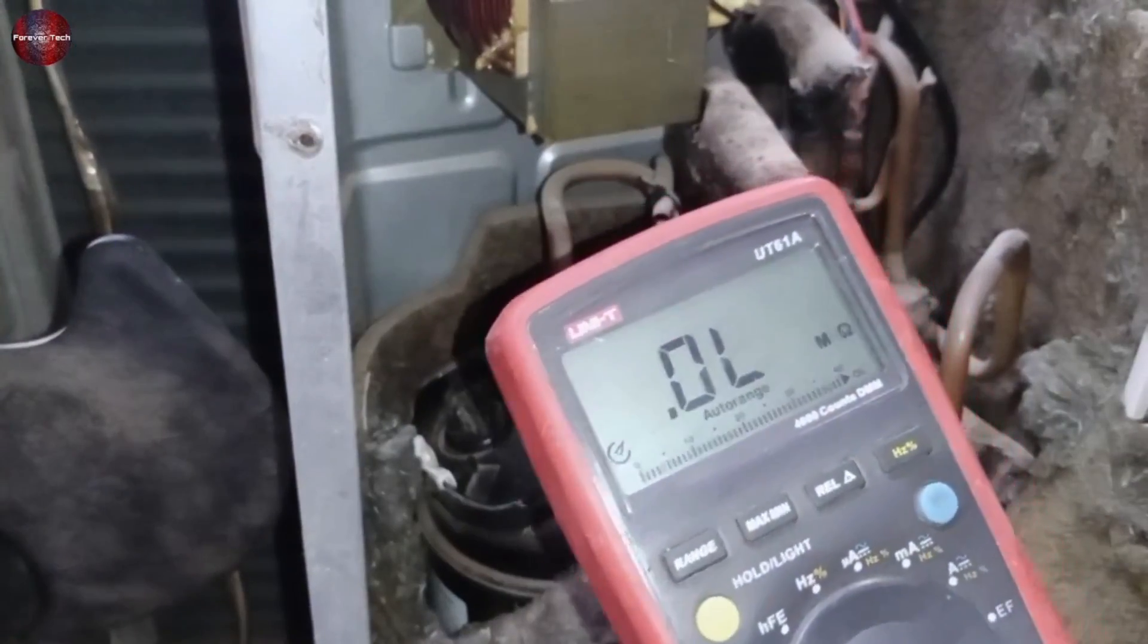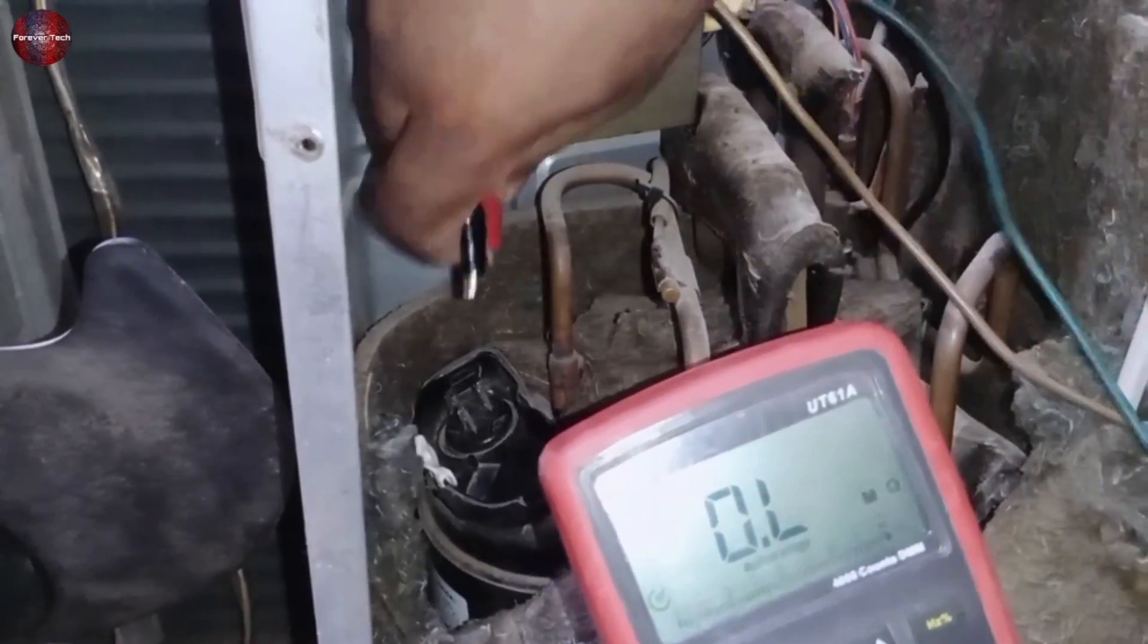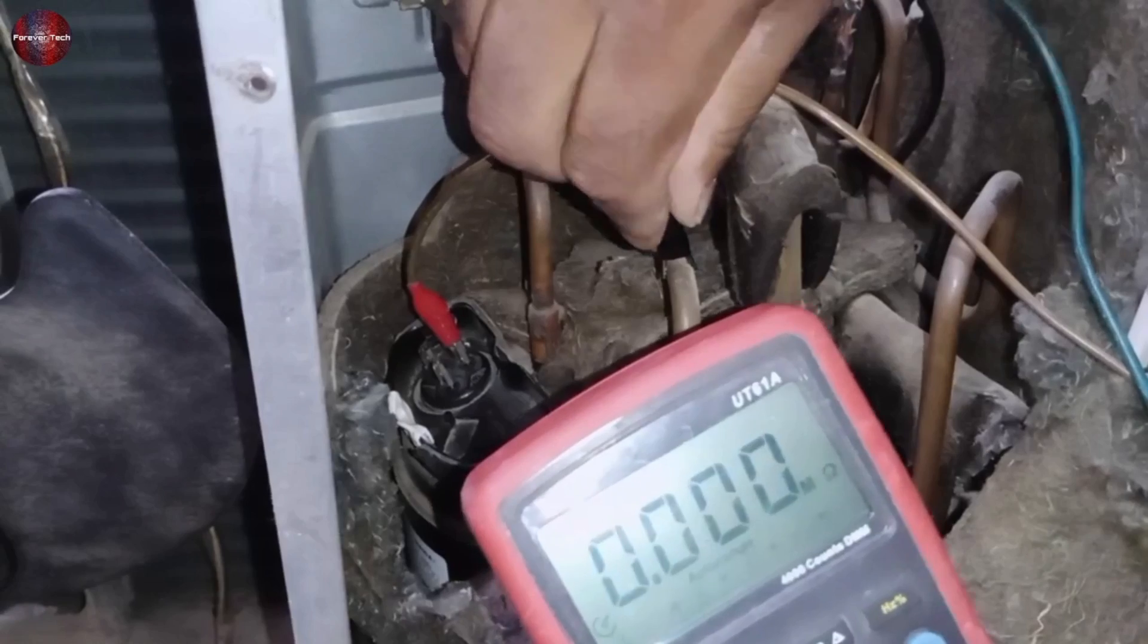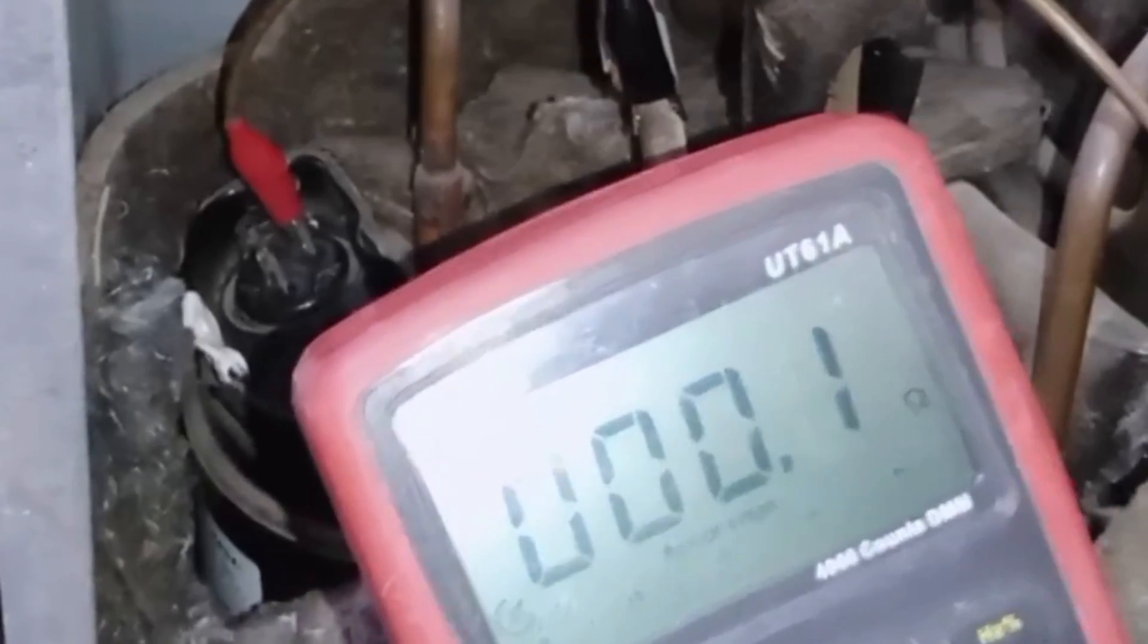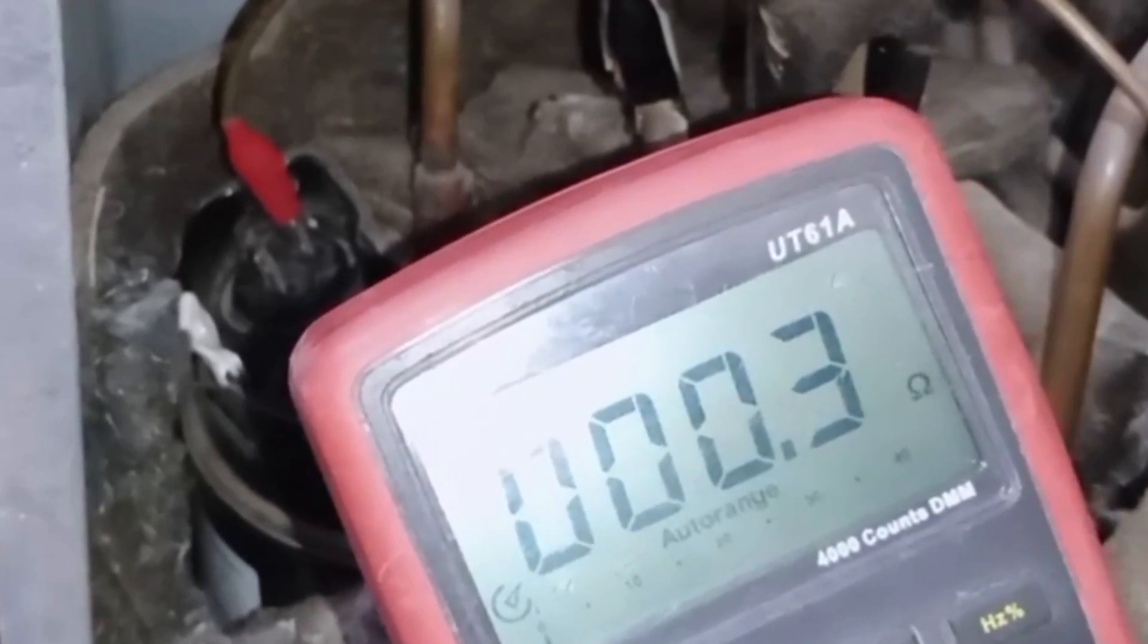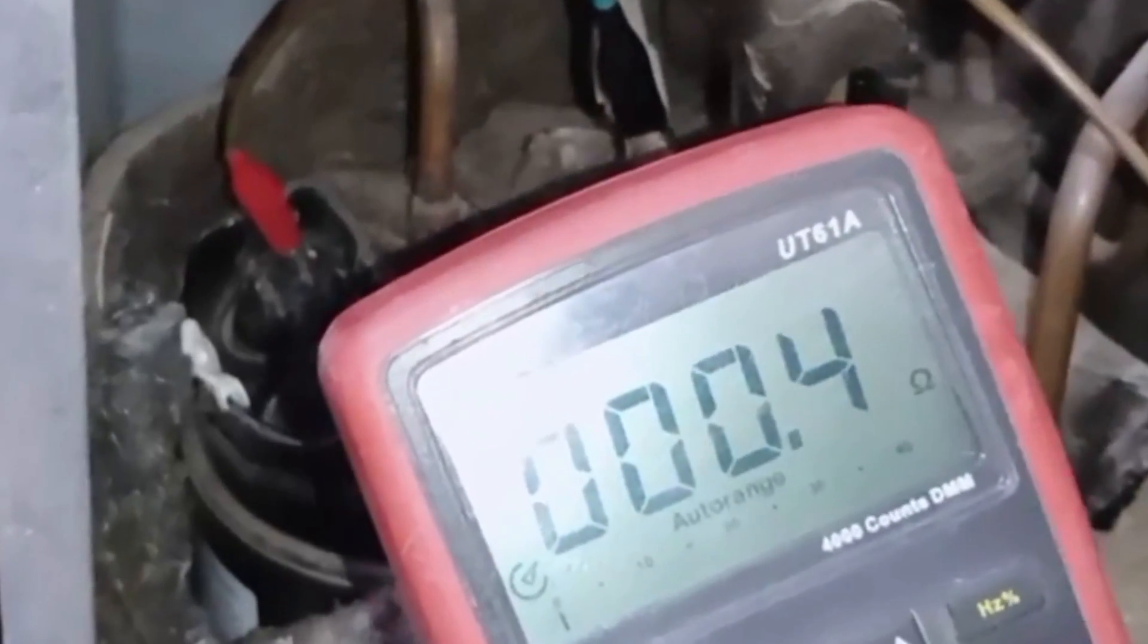Again set the multimeter on ohms and attach any one probe of the multimeter with the terminal of the compressor. And when we touch the second probe with the pipe body, the multimeter is showing us a reading. See, its winding has been leaked and shorted.